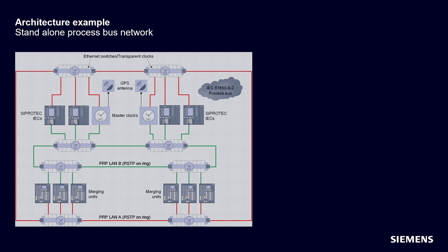This was taken from our process bus manual. And this is the configuration that you will use when you have substations with a higher amount of devices. So you will have to use different switches, and the way to connect them is using RSTP rings. So keep in mind that this configuration is a PRP configuration.